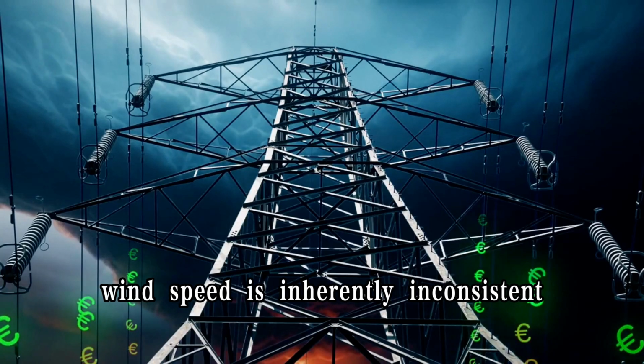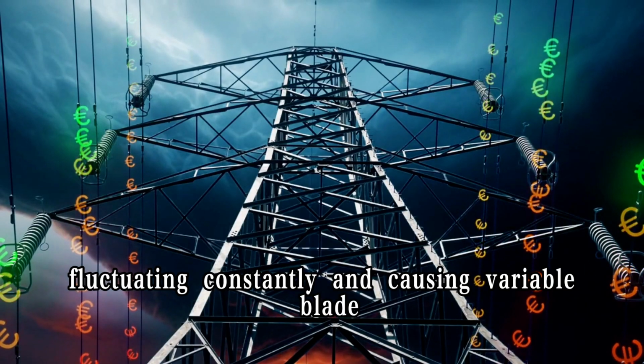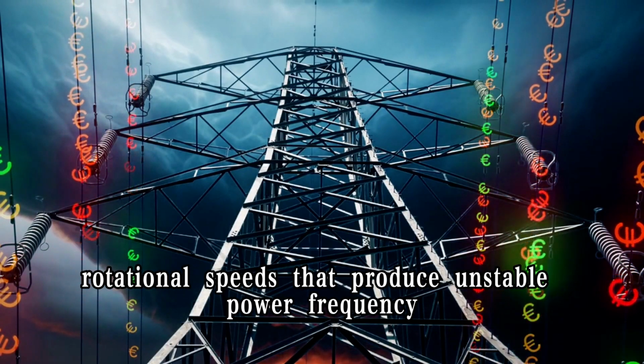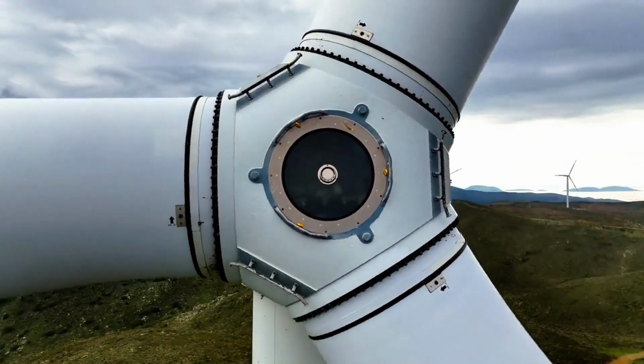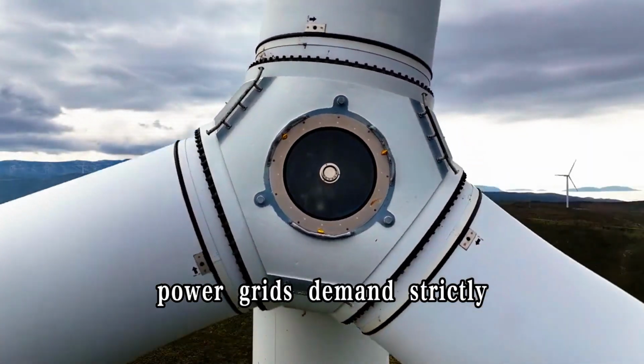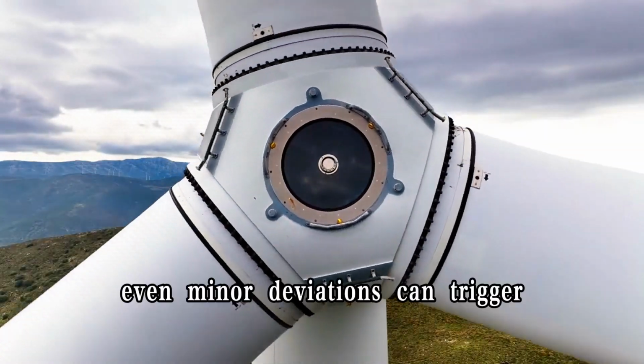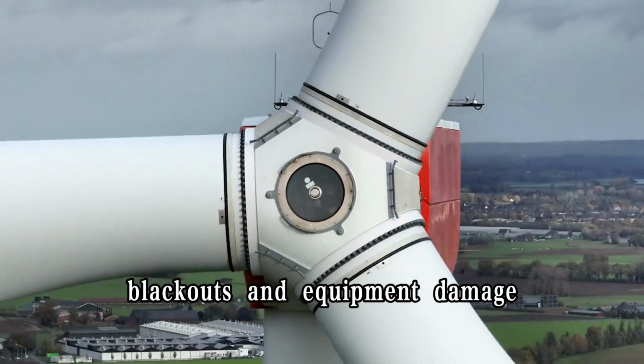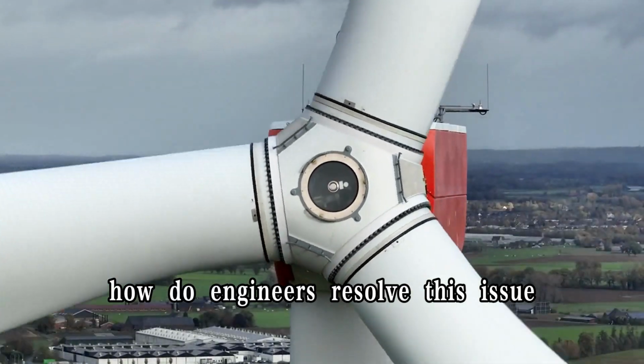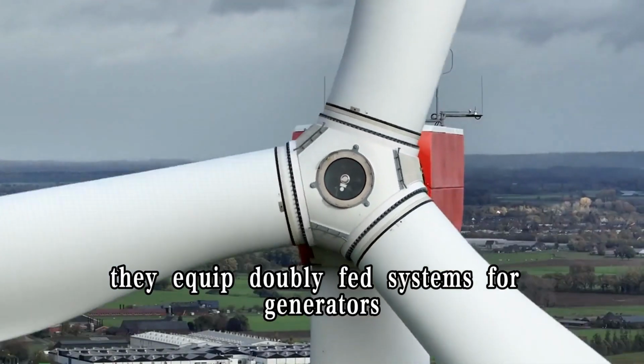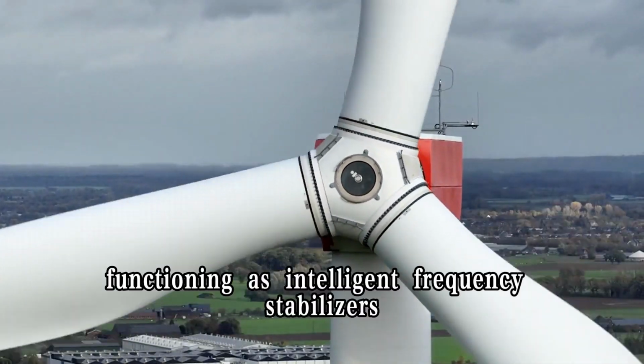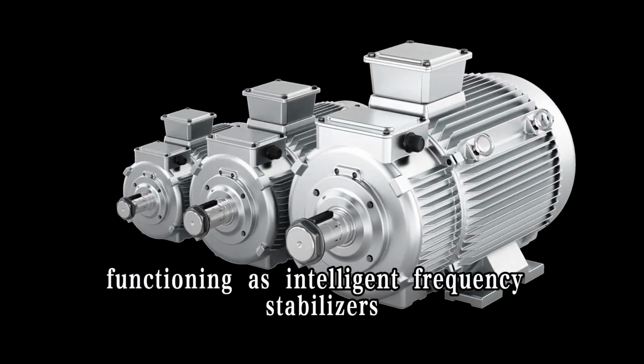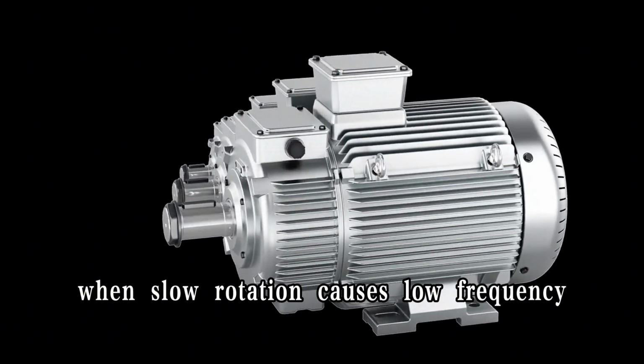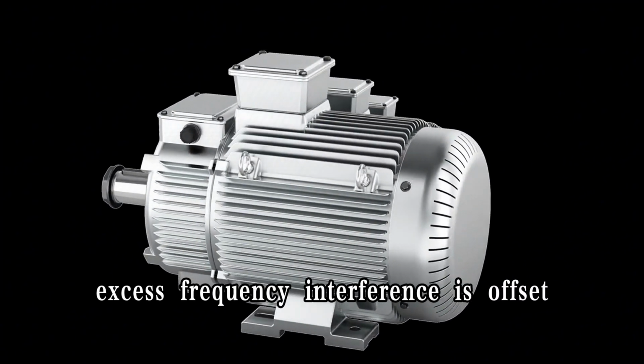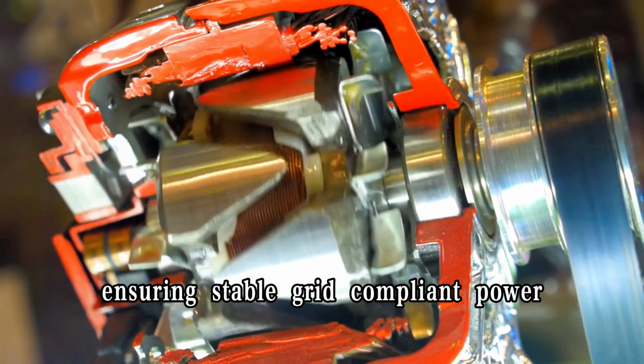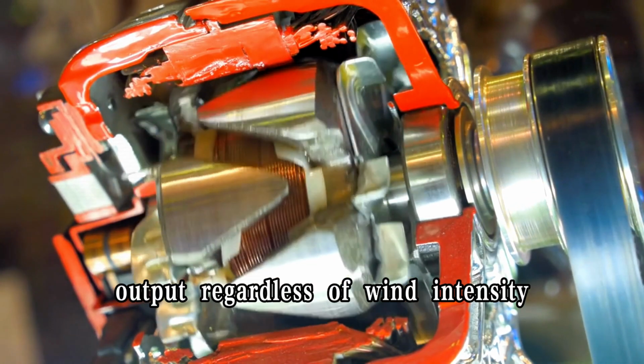Wind speed is inherently inconsistent, fluctuating constantly and causing variable blade rotational speeds that produce unstable power frequency. Power grids demand strictly precise frequency parameters. Even minor deviations can trigger blackouts and equipment damage. How do engineers resolve this issue? They equip generators with doubly fed systems, functioning as intelligent frequency stabilizers. When slow rotation causes low frequency, the shortfall is compensated, and when rotation is fast, excess frequency is offset, ensuring stable, grid-compliant power output regardless of wind intensity.